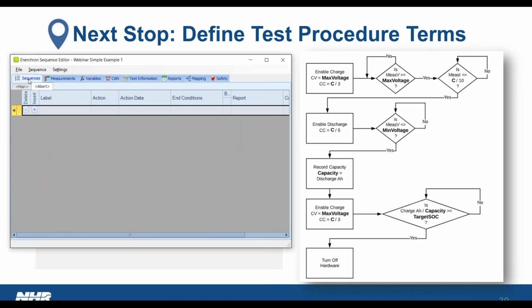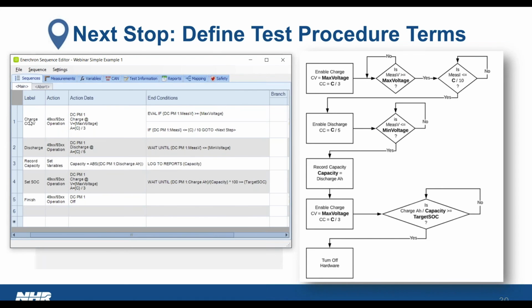If I slide over and select the Sequences tab, it contains the logic—for example, setting the operation of the hardware for the power module, enabling it for charge, with a voltage setting equal to the maximum voltage, and a current setting equal to C divided by 3. Again, we can use the terms and formulas directly inside the test. Looking at the end conditions for this step, we evaluate if the measured voltage is greater than or equal to the maximum voltage, and if so, also evaluate if the measured current is less than C over 10 before going to the next step. So it would stay in this charge state until reaching those end conditions.